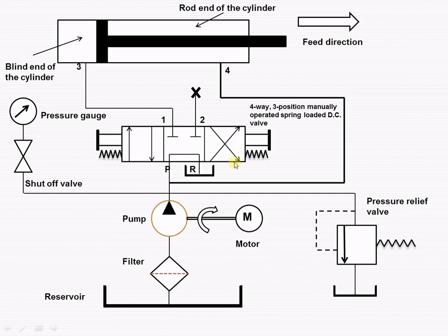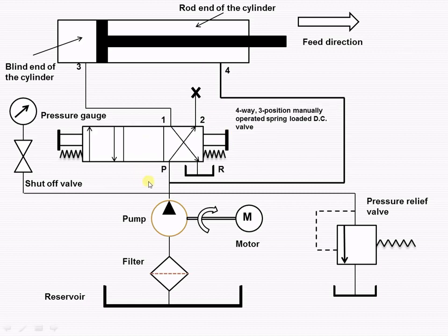When we operate the direction control valve such that the spool of the four-way direction control valve is in the right envelope mode, from port P it tries to go to a particular port but it is blocked. So the fluid enters into the rod end of the cylinder, causing retraction, and the liquid from the blind end from port 3 exits and from port 1 goes to port R.